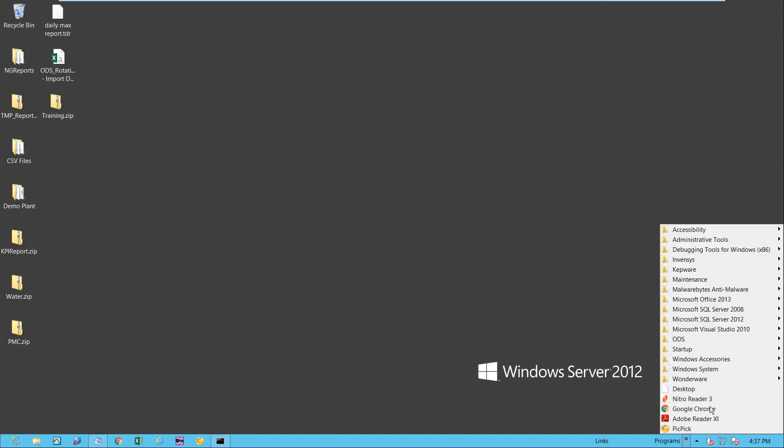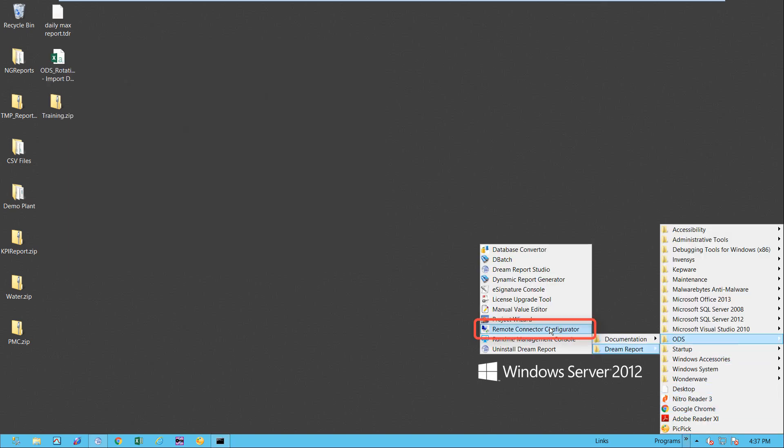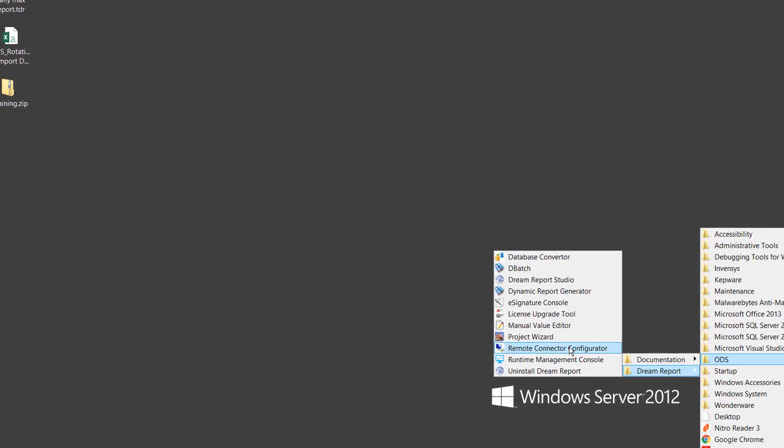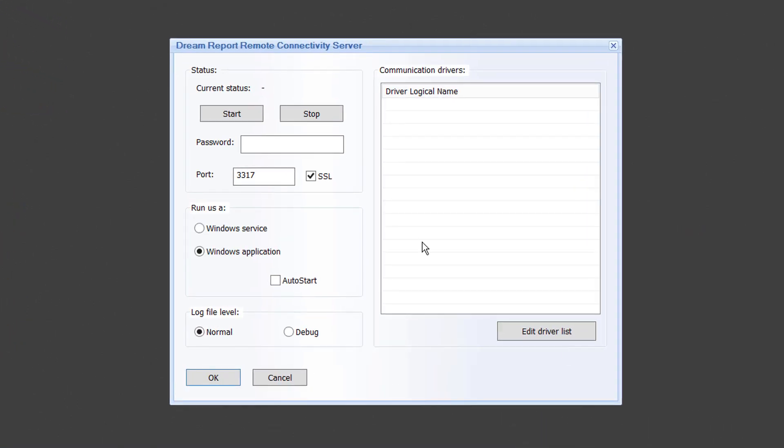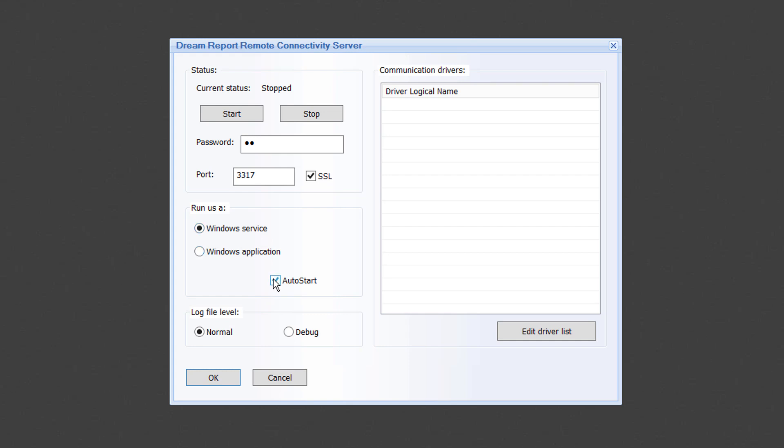I will launch the remote connector configurator from the ODS program group. Here I am going to specify a password that the remote driver on the DreamReport side will need to connect with. I will specify a port through which to communicate and whether SSL or Secure Sockets Layer will be used. Make sure to verify that the specified port is available and open if a firewall is in place. This is the most common reason when troubleshooting remote connector problems. I will also specify that the remote connector will auto start and run as an application or a service.